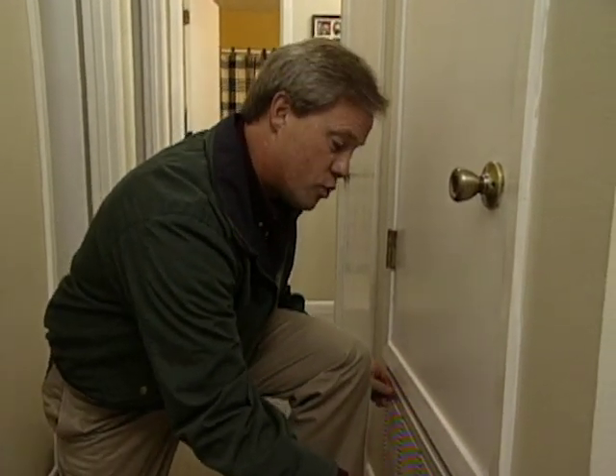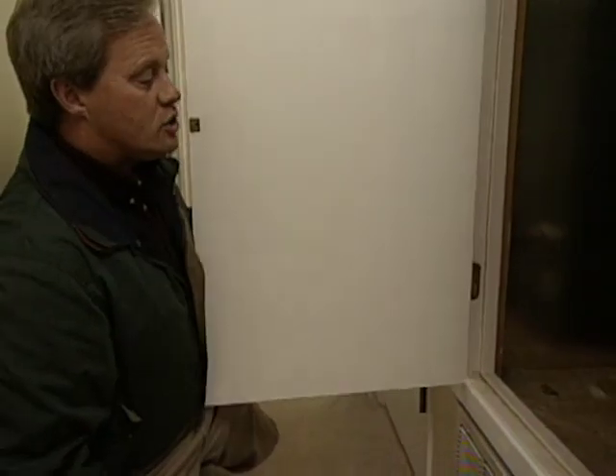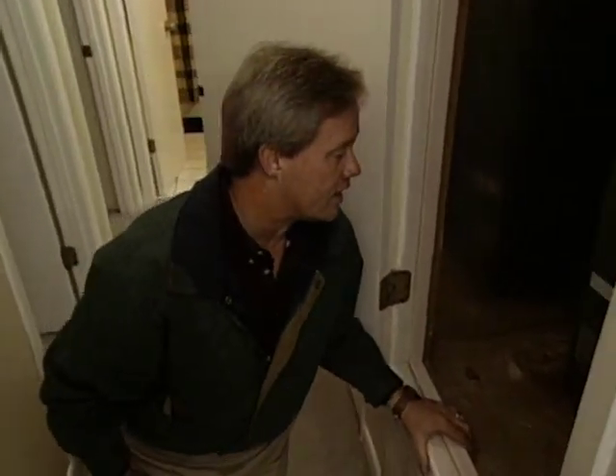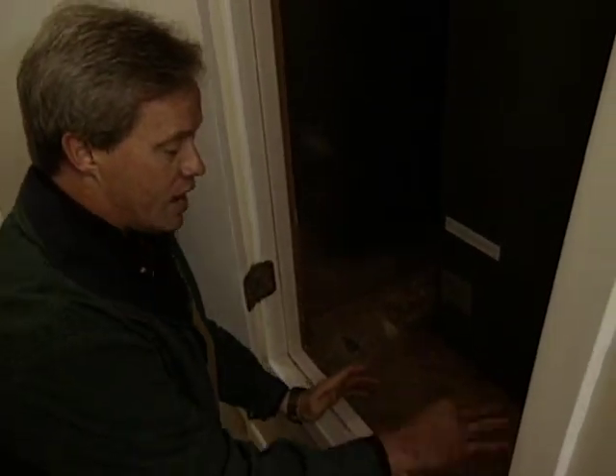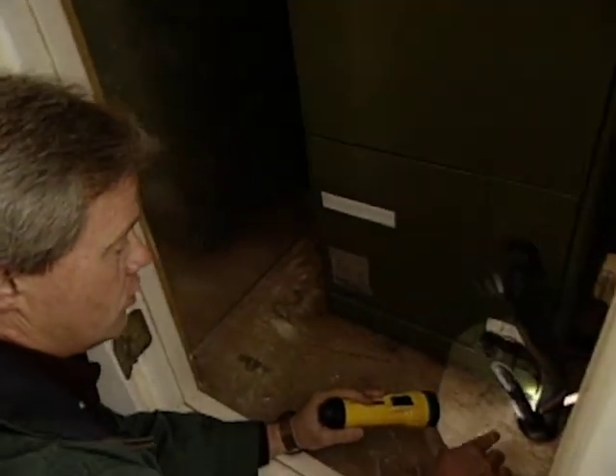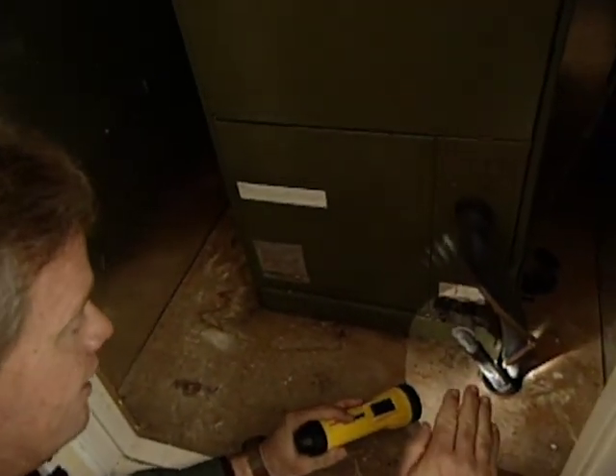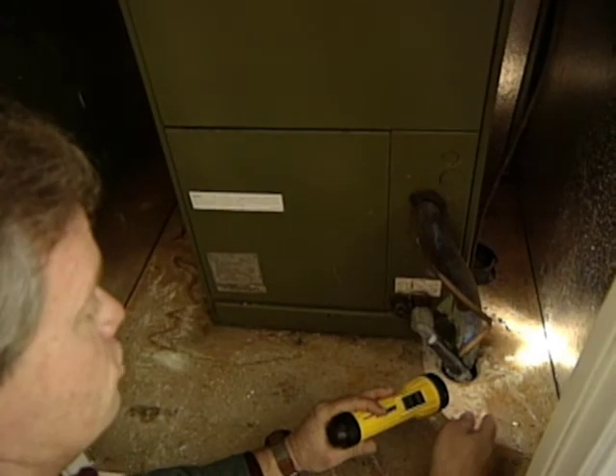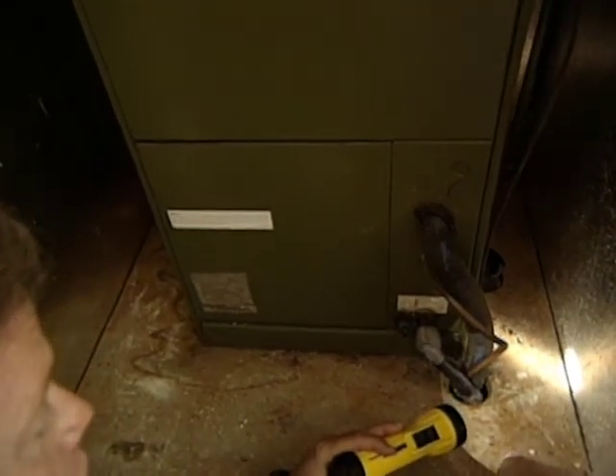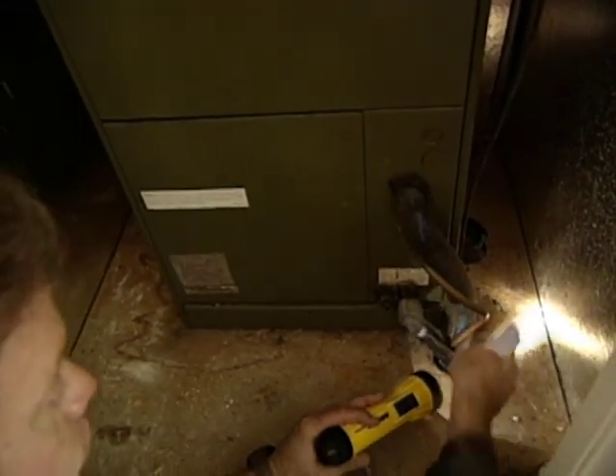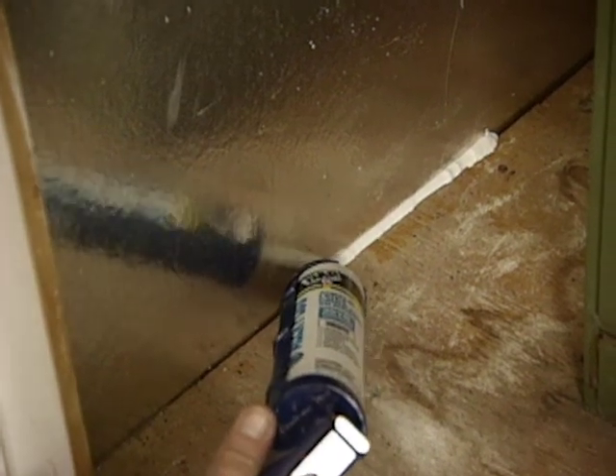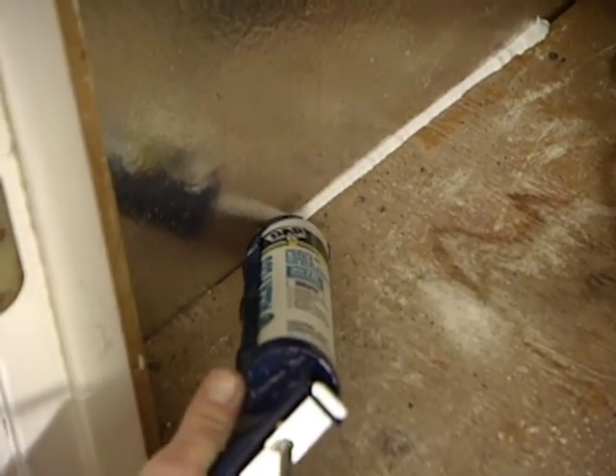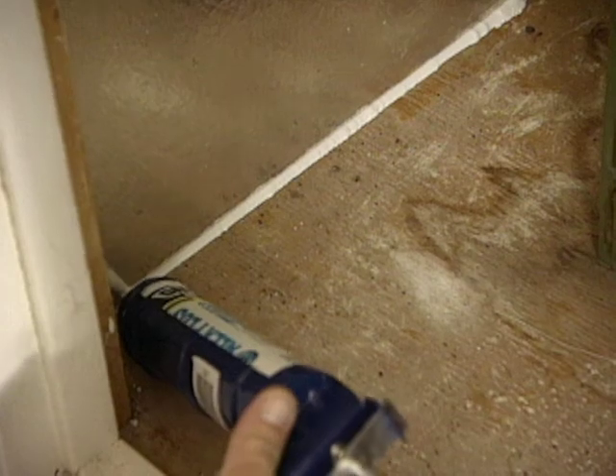But in order for your unit to be using only filtered air, it's a good idea to inspect an area like this, because if you have any holes like right here, it's allowing air to get down through this platform, and the unit is bringing in unfiltered air. The same goes for any little cracks along the platform like we have here. We need to take some caulking and seal all of this up so that every bit of air going into your unit is going through the filter.